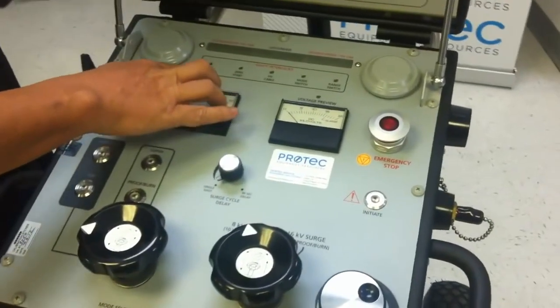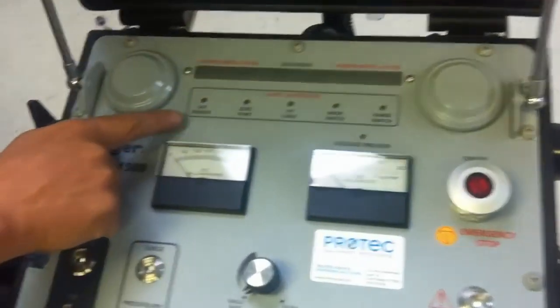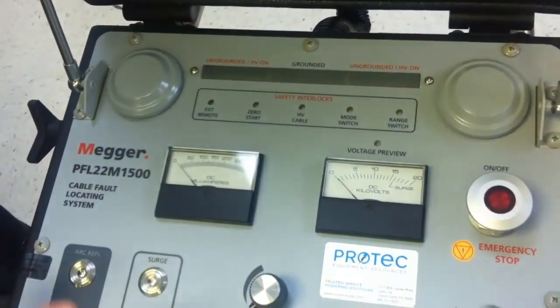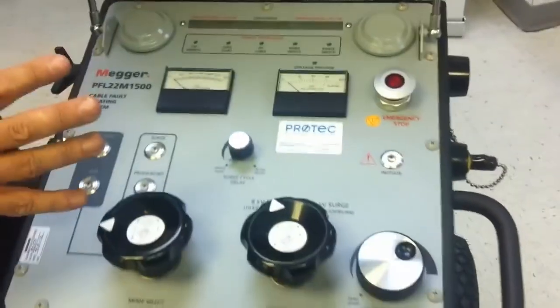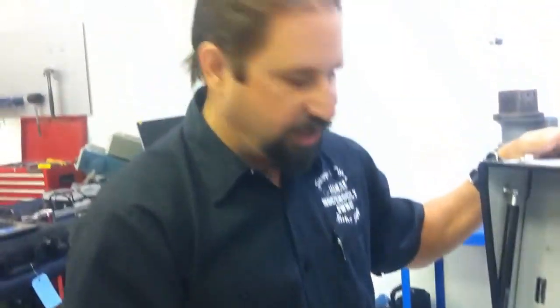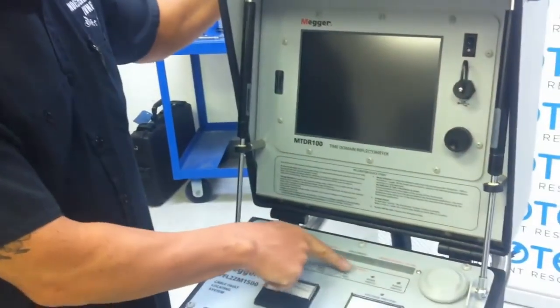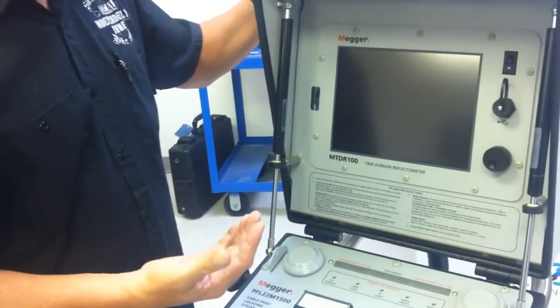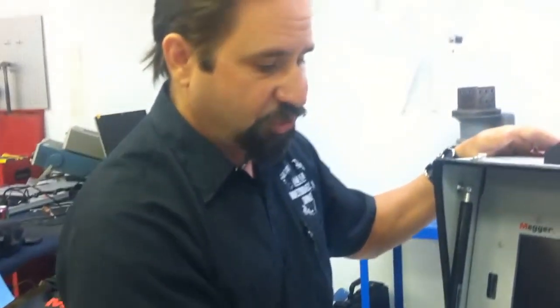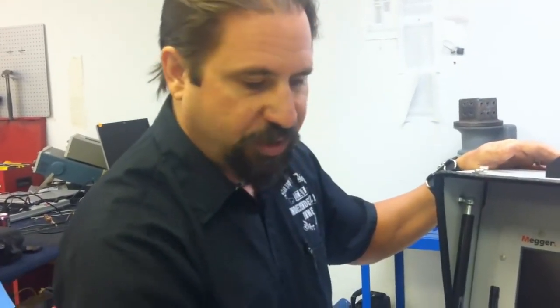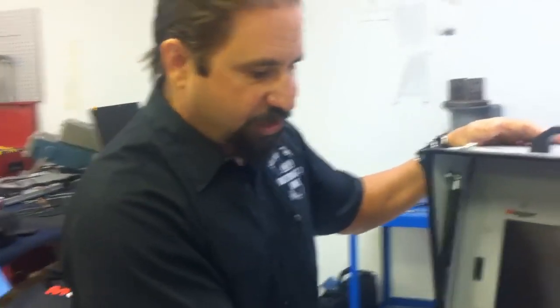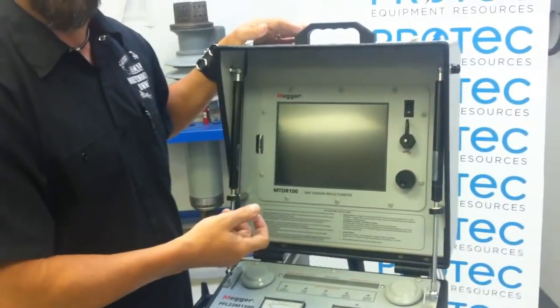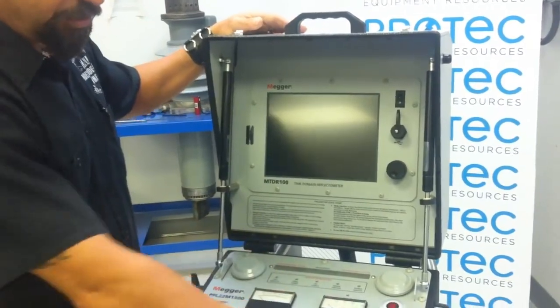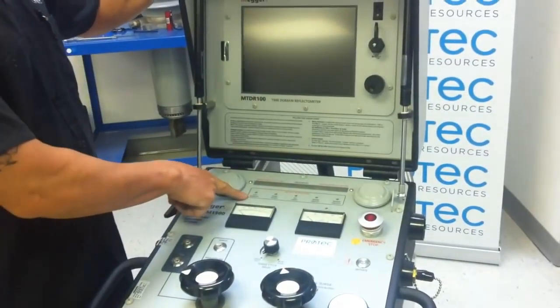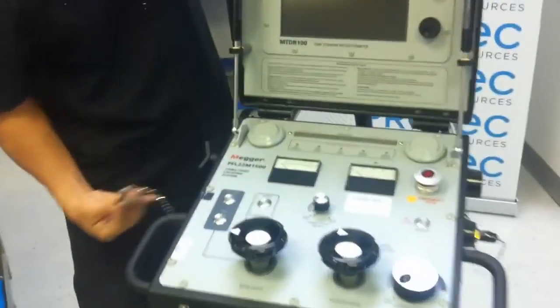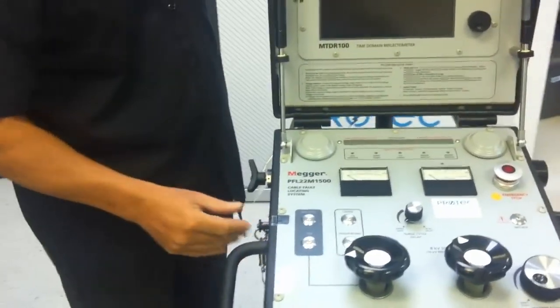Megger has also done a very nice job of giving safety interlock notifications. If any of the top panel control settings are not done to the safety performance of the instrument, the associated lamp will illuminate, immediately alerting the end user to check your mode switch, check your range switch, which may not be properly seated, check your high voltage cable, is it properly plugged in and connected, check your zero inner start, or check your external remote and interlock switch.